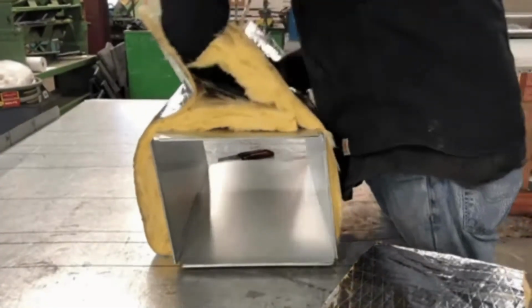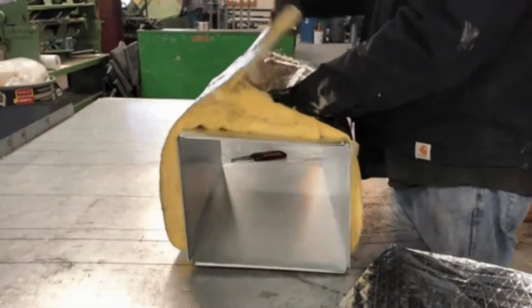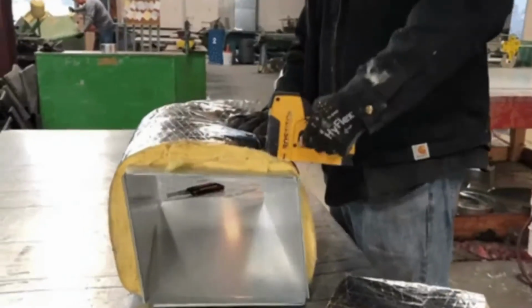Now, we use sheet metal plenums. So the question now is whether you line it, or you use a fiberglass insulation on the inner part of it, or you just wrap it on the exterior. I prefer to wrap the exterior. I like to keep the inside of the ductwork, that metal, clean. I don't want the fiberglass fibers up inside there with the duct liner. Even though they're approved for air flow, they're not supposed to give off pieces. But like I said, I don't like to have them insulated on the inside. I like to insulate them on the outside.